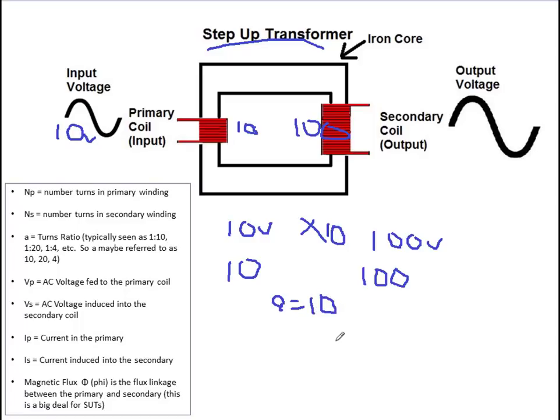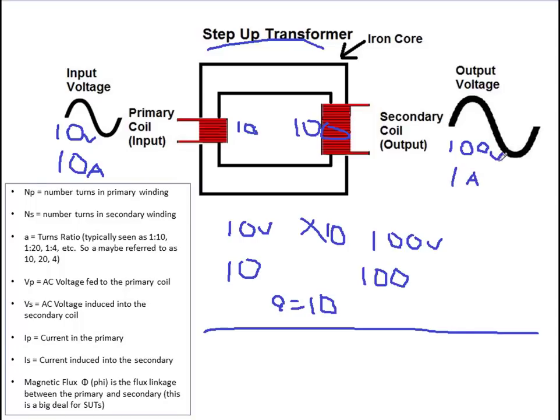One thing I didn't tell you is that the current does the inverse. So if we fed the primary with 10 amps—10 volts at 10 amps—on the secondary we'd get out 100 volts at 1 amp. It's just the opposite: as you're multiplying voltage, you're actually dividing current. In other words, you're giving up something to get something. So 10 volts in gives you 100 volts out, but if that 10 volts took 10 amps, it would feed out only 1 amp. That's not a problem for us, and you'll hear why in a minute.